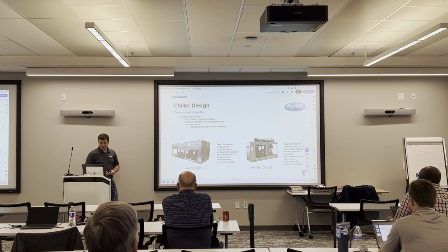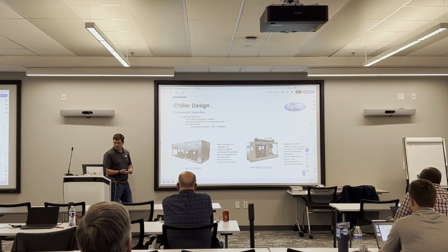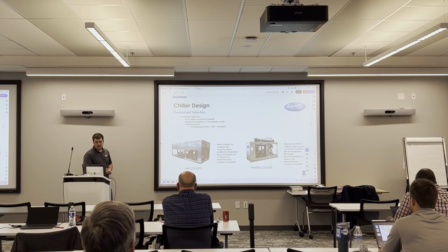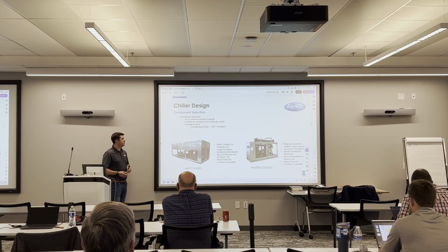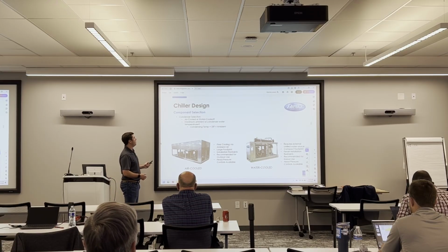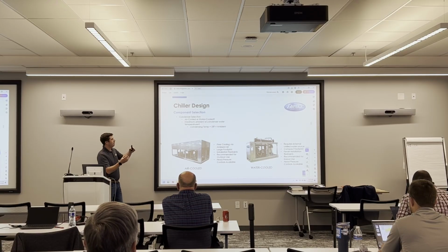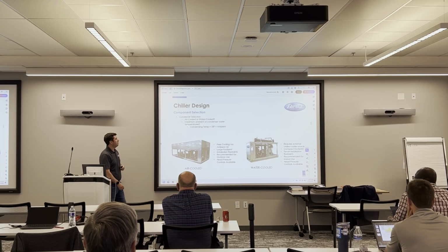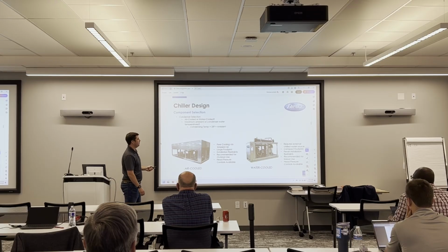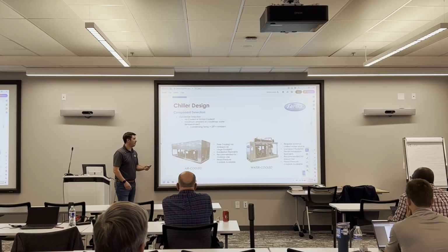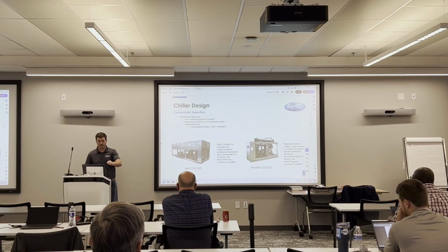All right, so that was the compressor. Now we'll talk condensers. So condensers get split between two different styles. You can either do an air-cooled condenser where you have a finned tube style heat exchanger with a fan. The fan's just taking ambient air, blowing across the coil. So that's essentially free cooling from the ambient air until our government decides that air is no longer a human right. We'll see.